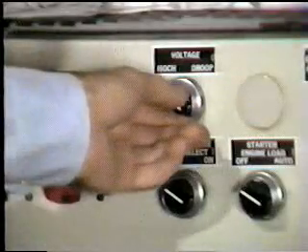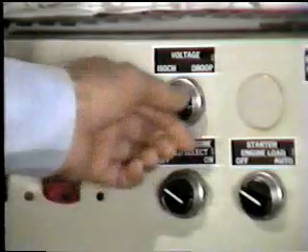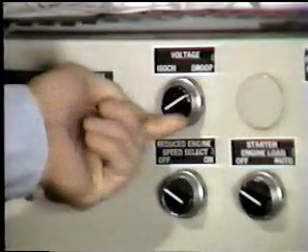Remember, the change in fuel flow only changes the amount of load each generator can carry. It does not change the speed of the engine. If engine speed were to change, the generator's output frequency would change from the needed 50 or 60 hertz. Now, you can select two modes of speed control for the governor by selecting either the ISOCH or the droop mode with this switch.